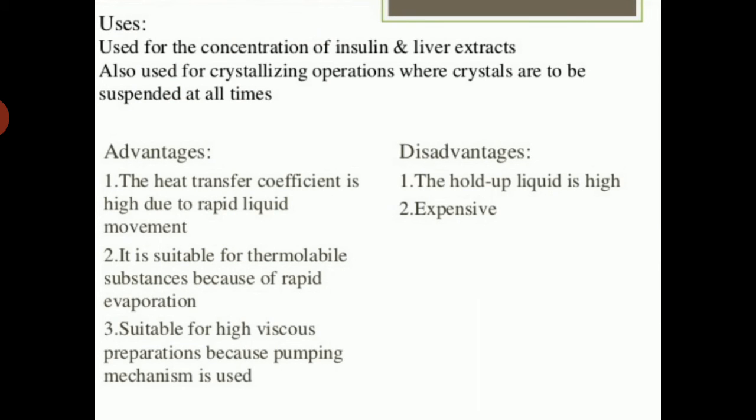Heat is transferred to the liquor through the walls of the tubes, and the liquid becomes vapor and forms smaller bubbles, which tend to fuse to larger bubbles. These are of the width of the tubes, thereby the bubbles trap a part of the liquid on its way up in the tubes. As more vapor is formed, the slug of the liquid is blown up in the tubes, facilitating the liquid to spread as a film over the walls. This film of liquid continues to vaporize rapidly.